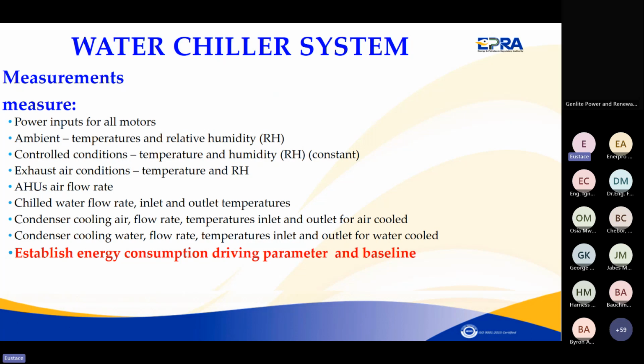Then for the condenser unit, you need to measure airflow if it's air-cooled, or water flow rate if it's water-cooled, along with inlet and outlet temperatures.